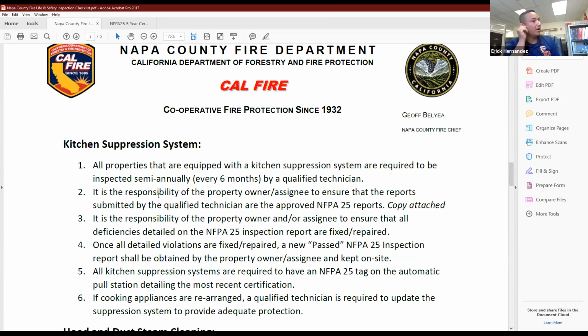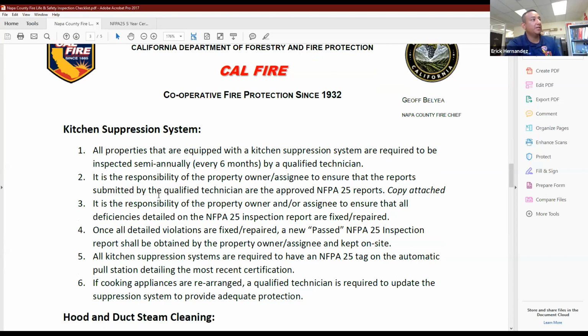So let's talk about, not all of these properties meet this, but if you do have a kitchen suppression system, these are the guidelines. All properties that are equipped with a kitchen suppression are required to be inspected semi-annually, so every 6 months, by a qualified technician. There's two things here. There's a pre-engineered kitchen suppression system, and there's a hood system. While they're both meant to protect the cooking equipment, there's two separate things.